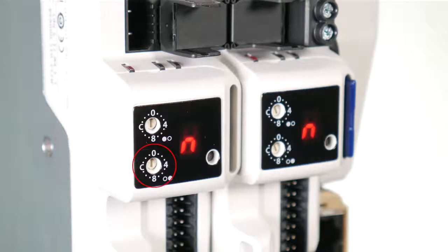by the bottom dial. The configured station alias or node address will be set to the sum of the most significant nibble and the least significant nibble in decimal. As the dials are adjusted, each setting is shown on the display.